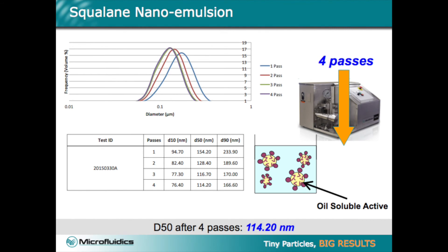After four passes, the microfluidizer was able to achieve a D50 of 114.2 nanometers. We hope you enjoyed this video, and invite you to contact us to set up your own proof-of-concept testing with your own formulation.